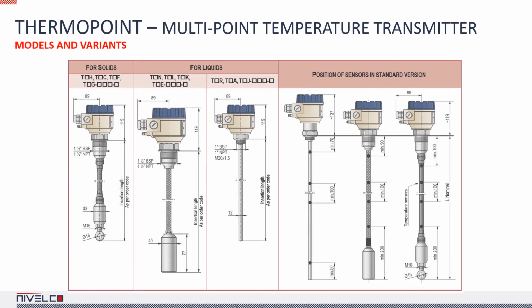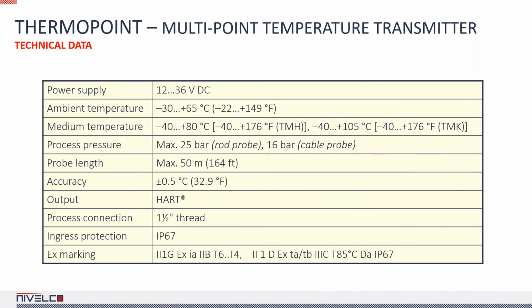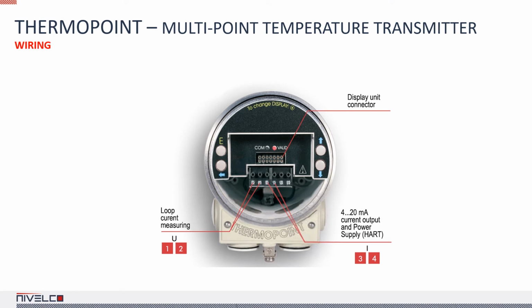The maximum number of integrated temperature sensors is 30. Their location can be determined by the user, although design rules must be considered. The maximum probe length is 164 feet. A solid-state temperature transmitter module is integrated into the measuring probe, so the system is not made of PT100 elements. The 4 to 20 mA output can be set to be proportional to the measured value of a single sensor, the average of the measured values of all sensors, or the highest measured value.